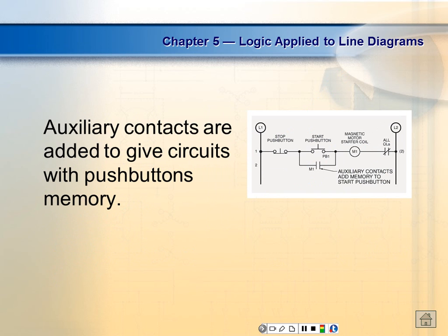Okay, auxiliary contacts. Everybody understand auxiliary contact? So the motor starter, if it's three-phase, is going to have three main contacts on that thing. And they're going to be pretty expensive because they're designed to handle a lot of current, right? Y'all understand that? But we move to this little sealing circuit over here. That stays inside the control diagram. That's not in the power, that's in the control.